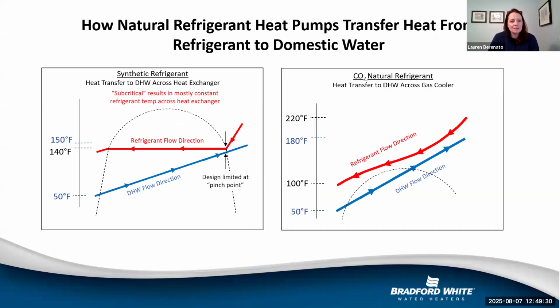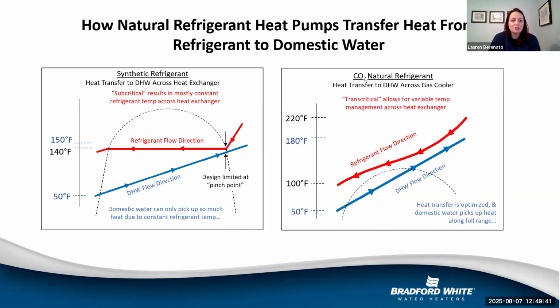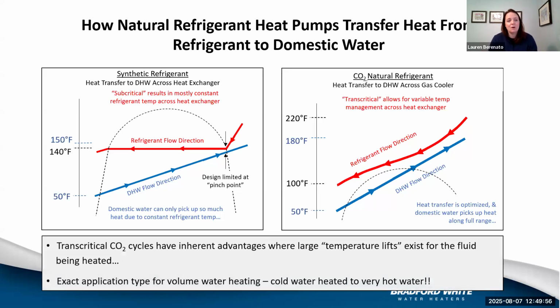Just more slides going on identifying how synthetic refrigerant operates differently from CO2 natural refrigerant, talking about the subcritical results that occur within these refrigerants, as well as transcritical, which will allow for variable temperature management across a heat exchanger. And then you also have differences in your heat transfer optimization. So you can see here the performance and flow of CO2 versus the synthetic. And then basically showing the differences how transcritical CO2 cycles have inherent advantages where large temperature lifts exist for the fluid being heated. Exact application type for volume water heating, cold water heated to very hot water is where you will typically see that.